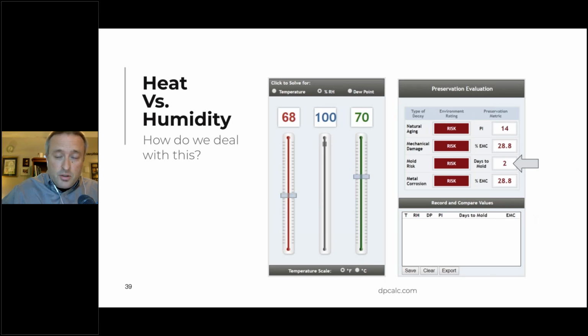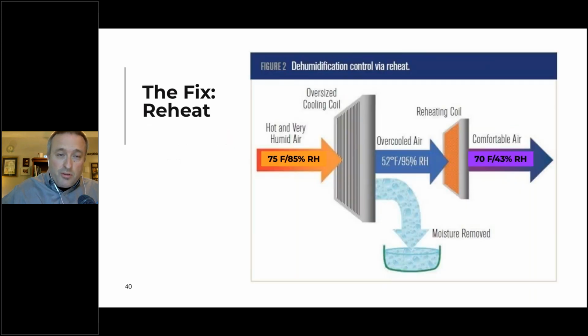So how do we deal with this? Remember, we don't have much cooling that we need to do, but we have a lot of dehumidification. So the fix is what's known as reheat dehumidification, or just reheat for short. And the concept's really simple. This is very common in commercial systems. It's very uncommon in residential systems, which is actually the main reason that I wrote this presentation, was so that I could badger manufacturers into adding this to their controls, because it's a software problem. It is not a hardware problem, as we'll get into.